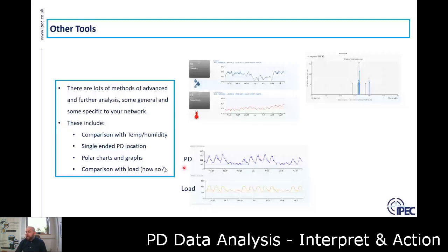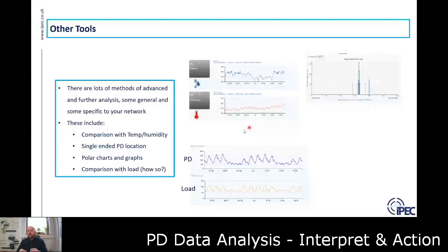Other tools include single-ended mapping, which allows you to perform PD location from your office without going to site — the monitoring system can conduct PD location by mapping from a single end of the cable. There are also other charts and graphs such as polar charts and polar graphs, and different ways to view PRPDs. Basically, there's a whole host of tools and techniques available, depending on the assets you're looking at and how advanced you want to go with PD analysis.